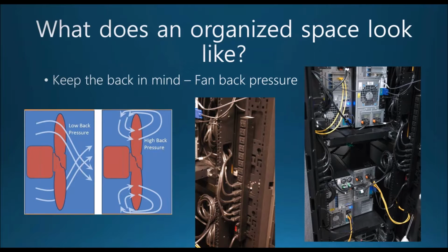The same goes for switches - they have little fans on the side trying to blow air out. If cables are hugging the unit, or cables come in the front and out the back creating a mess from all those power cables, the unit can't bring fresh air in and blow it out the back. That's tougher on the fans, and they'll fail. Again, that heat issue can lead to capacitor plague, whether on a server or a network switch.